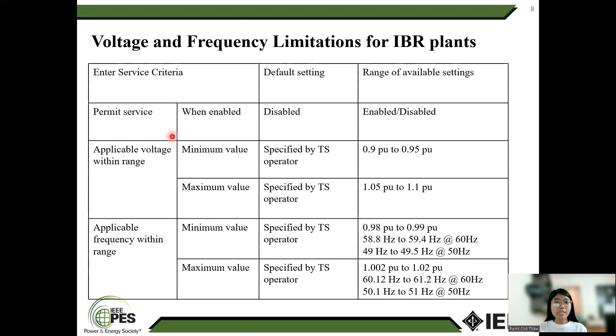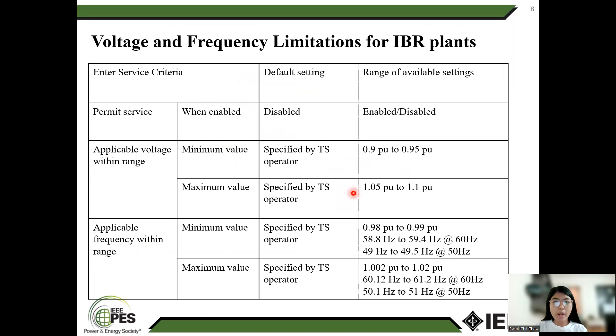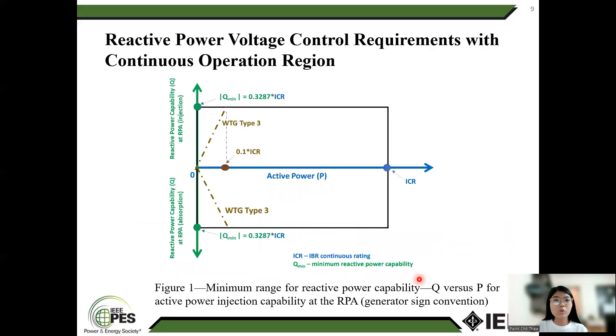Voltage and frequency limitation for IBR plants: when entering service, the IBR plant shall deliver power to the transmission system. The applicable voltage and frequency shall be within the range specified. Applicable voltage within range: minimum value 0.9 to 0.95 per unit, maximum value 1.05 to 1.1 per unit. Applicable frequency within range: minimum value 0.98 to 0.99 per unit, maximum value 1.002 to 1.02 per unit.